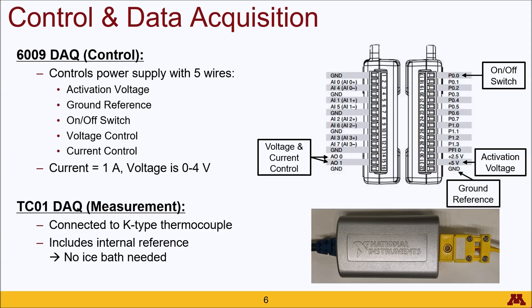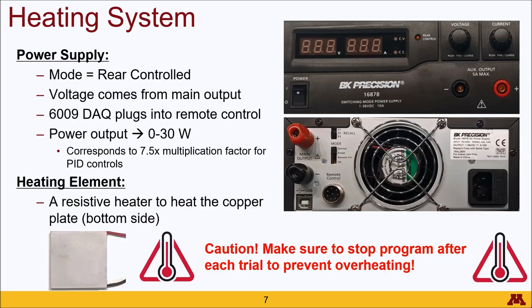The TC01 DAQ is a thermocouple-specific DAQ connected to a K-type thermocouple. The reason we have a thermocouple-specific DAC is because it includes an internal reference, which means that you do not need an ice bath.